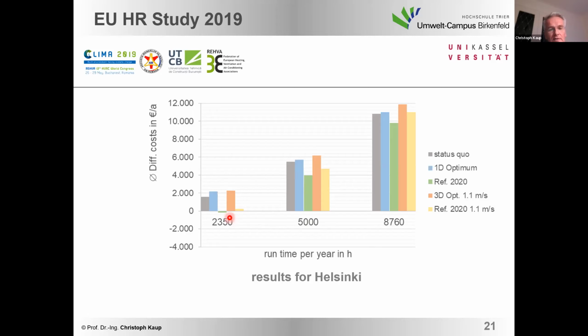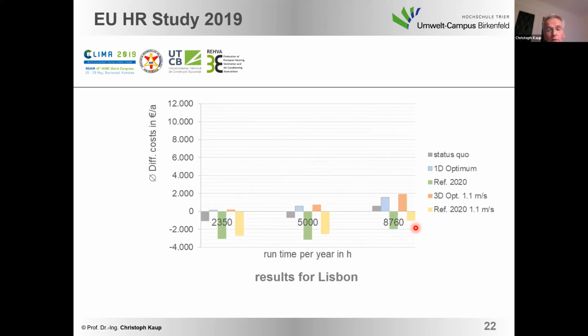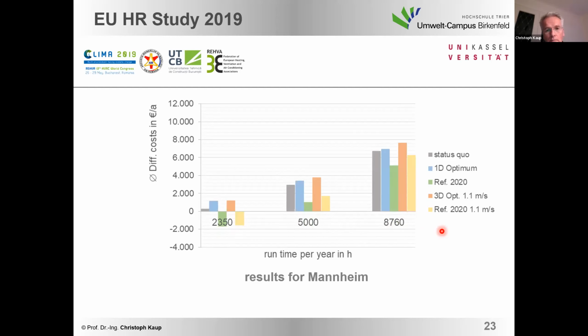And you see in Helsinki, we have still the slope between the operating times, but you see that with the reference conditions, we would produce more or less losses in offices, vice versa. In 24/7 operation, we could use it, but for sure the higher amount of savings we would reach with the optimized heat recovery system, not with the standard conditions. But if you look to Lisbon, for example, you see, now it's getting hard because we will produce losses in all kinds of situations with the reference values, with the benchmarks of the regulation. And for sure, the potential to recover heat is much, much lower in the southern part of Europe, Mannheim something in between.